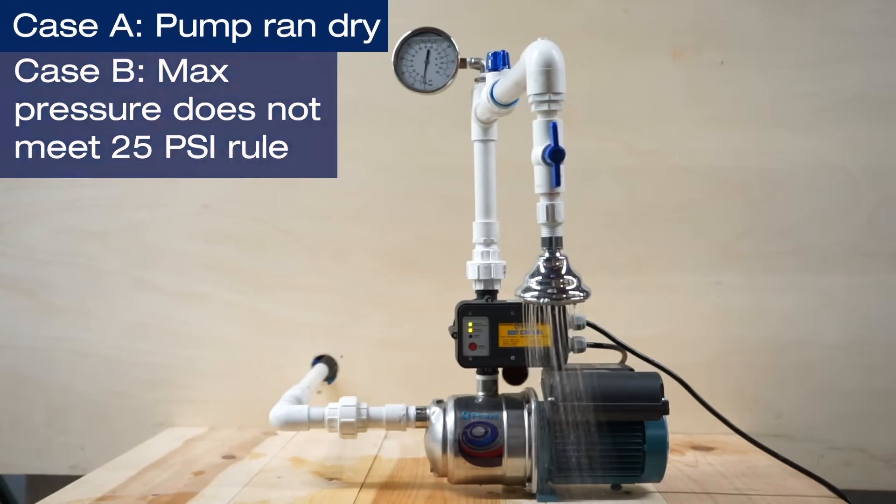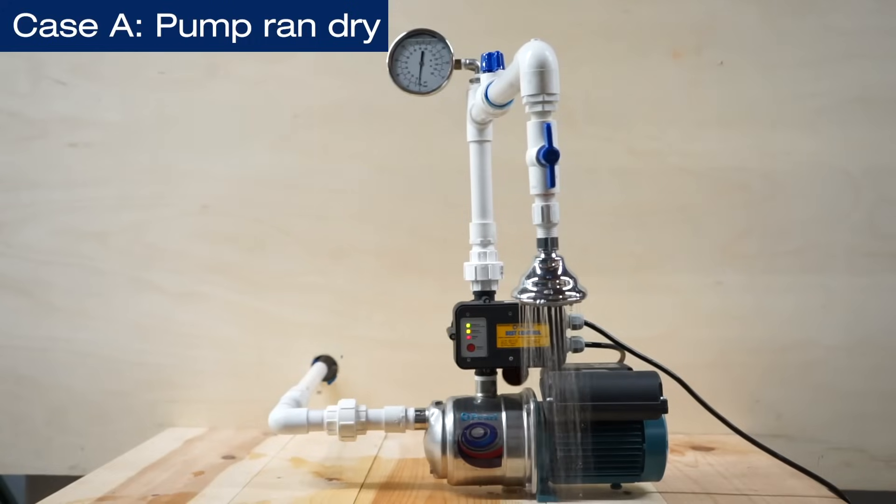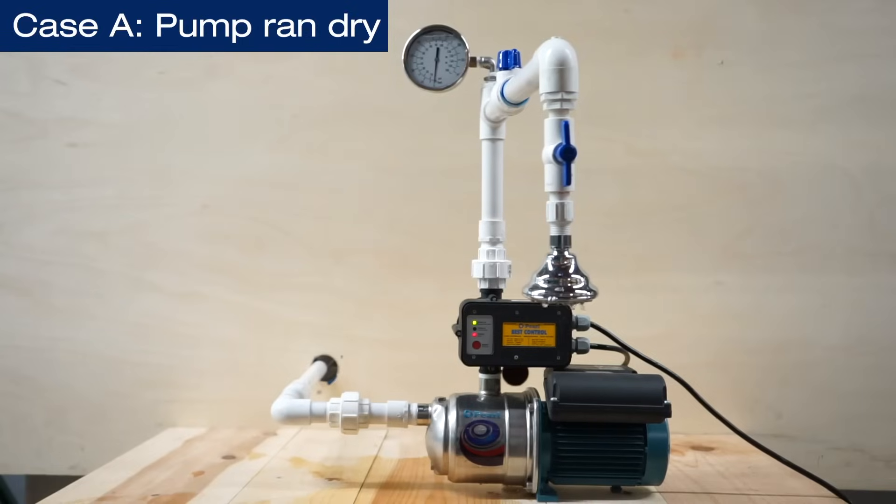In case A, if there is no water at the source, the pump will go into failure mode. Normally the pump will try to turn on automatically 5 times within 1 hour to try to resume normal operation. If there is no water available, the pump goes into failure mode.